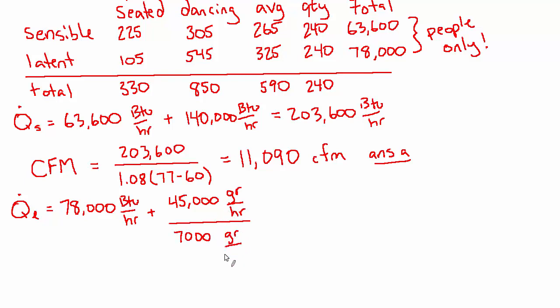There's a couple things we can do. The first thing we can do is divide that by 7,000, because there are 7,000 grains of moisture in one pound of water. So we'll say pounds of H2O and that will get rid of grains. So now we have pounds of water per hour. But how much energy is in a pound of water? Well, that depends on the enthalpy that has to be added in order to change phase, or the energy that's given up when water vapor condenses. It's the same amount of energy that has to go in to evaporate water as comes out of water when it condenses, and we call that the latent heat of vaporization.